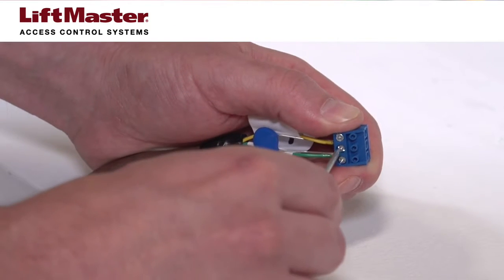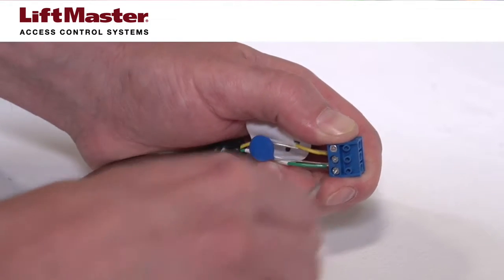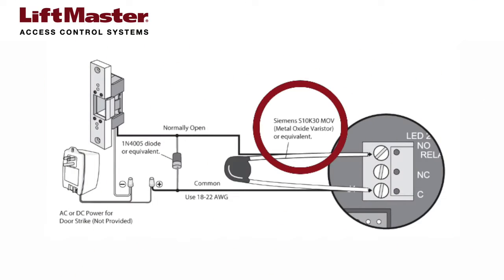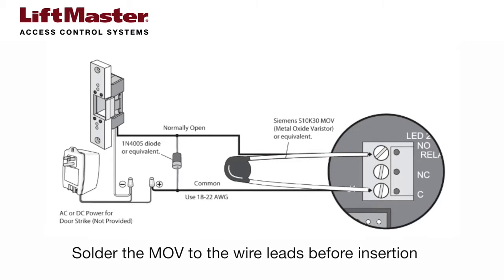If the door strike uses an AC power transformer, connect a Siemens S10K30 MOV to the common and normally open terminals on relay 2. It's best to solder the MOV leads to the wire leads.